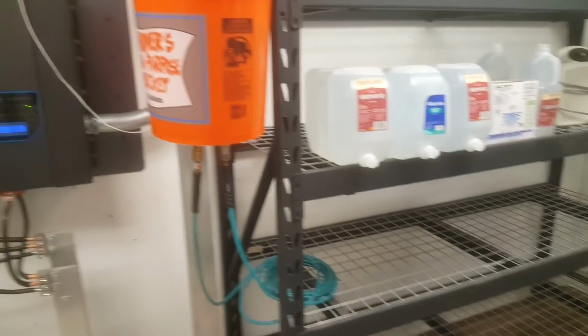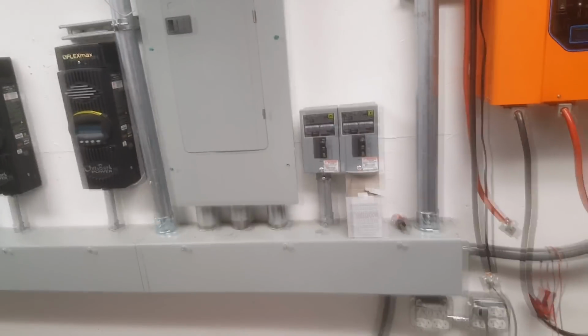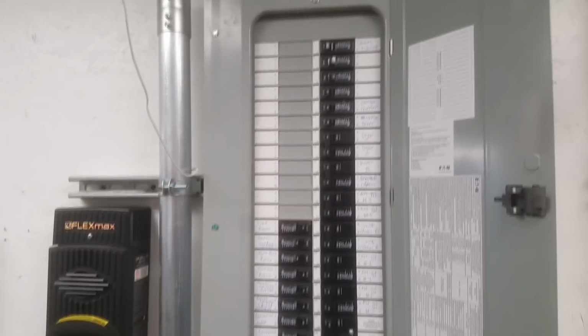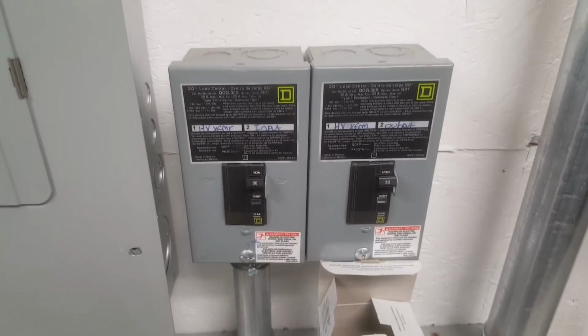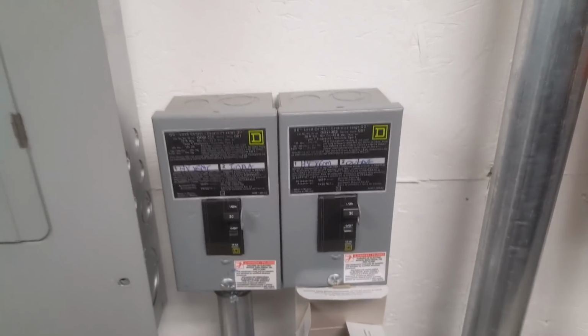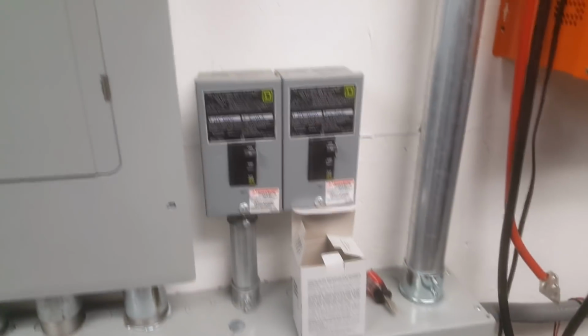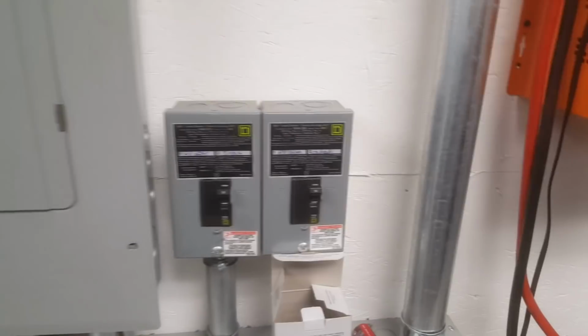hours of capacity for storage. And from this pull box, I come through this EMT here into these 3-foot sections of gutter. I have 4 of them, and the output of the inverter comes into this panel, and inside this panel it comes into this main disconnect, and from there it's branched out to various different circuits. Here I have 2 smaller disconnects, and these are for the generator. I have 2 of the 2,000 watt Honda inverter generators and 1 3,000 watt generator, and they come into this 30 amp breaker at 120 volts.